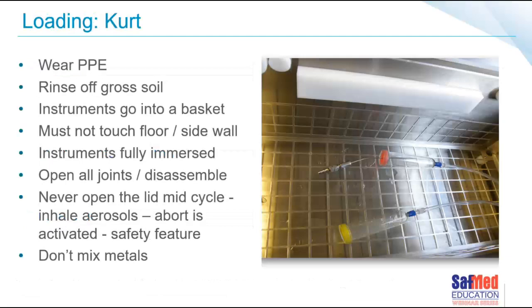Yes. So obviously, again, you spend time in the CSSDs. You see us using the pieces of equipment or loading instruments into the bath. Tell us about what the right processes are, or tell us about the things that you've seen that have gone wrong. Sure. So, okay, starting with number 1, wearing the correct PPE. We are always under pressure in the CSSD area, and we move from one section to the next, so moving from an instrument washer to the ultrasonic cleaner. A lot of times we forget to wear the correct PPE. We are on the dirty side of the CSSD, the decontamination side, and we need to wear the appropriate PPE. And this is to protect ourselves.